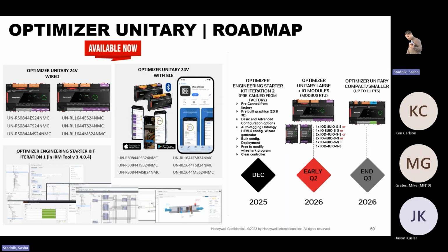Okay, so what we're going to do is, remember yesterday I was talking about Modbus IOs by DIP switch? Remember you have a Modbus port on this controller? So what we're going to do is the 8 UIO and the 4 UIO with and without display will be able to pair with this controller. Now, will it pair with the touch flex? Nope. There's no touch flex in the unitary. So how are you going to do it? Via Modbus.